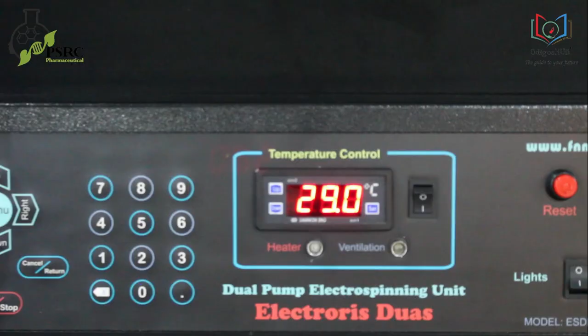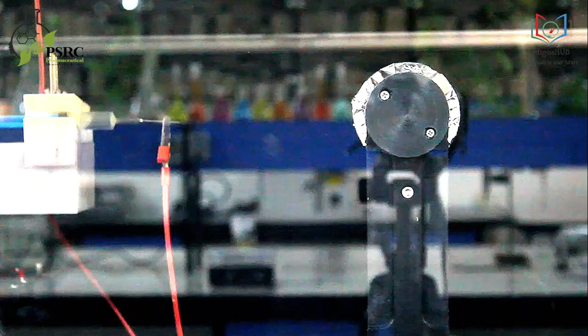As we mentioned in the theory part, when the jet is initiating, the solvent of the solution is going to evaporate. You know that some of the solvents are toxic and they may damage the respiratory and visual system. So, this ventilation system is installed to take out these harmful evaporated solvents for more safety. The electrospinning process is starting. Have a closer look at it, clearly see the solution being stretched out to the rotary drum collector. The fiber will collect on your drum during the run.